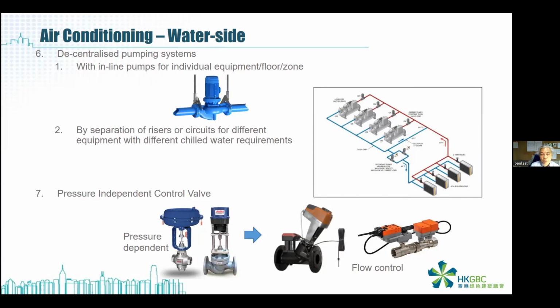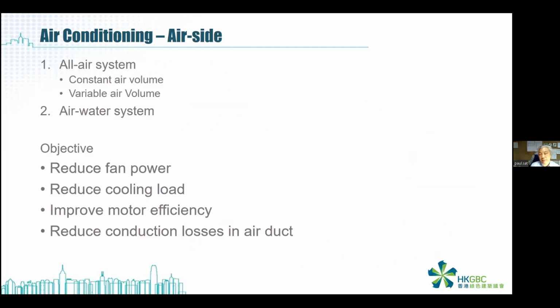As you know, for existing buildings in Hong Kong, between summer and winter, the cooling load requirement ratio is, let's say, 1 to 5, or 1 to 10. In winter it is 1, in summer it is 5 or 10, 5 times that of winter, something like that. So only a very small amount of flow rate is required. But if you use the conventional pressure dependent valve, you cannot achieve this. So this is the water side.